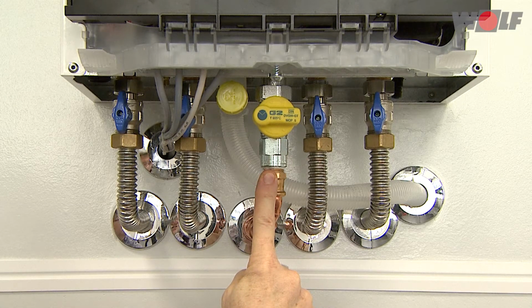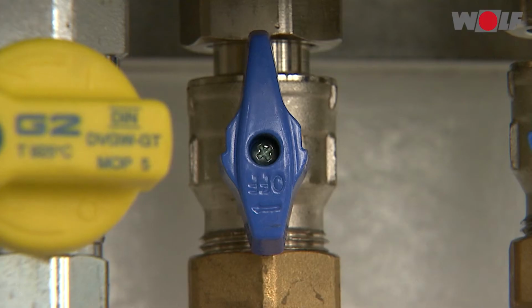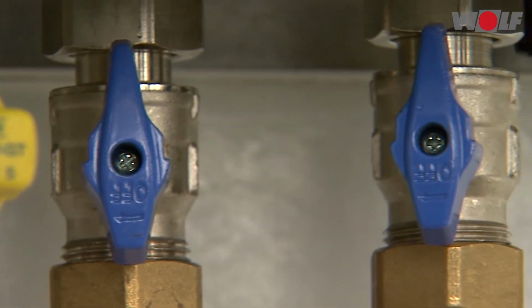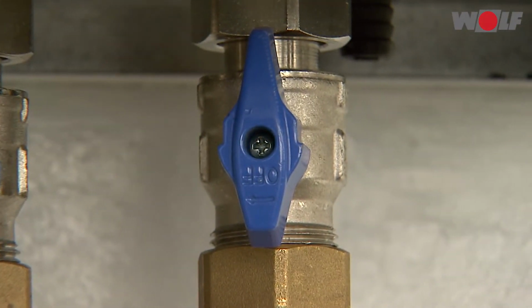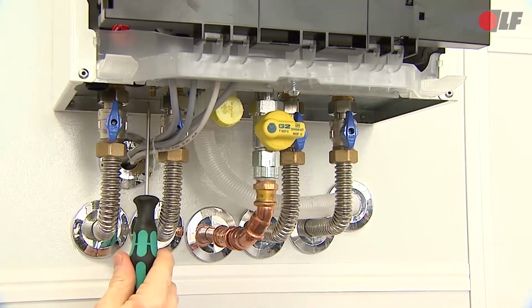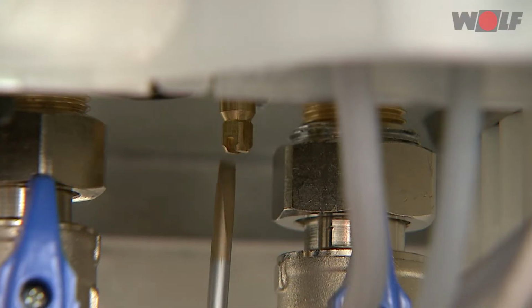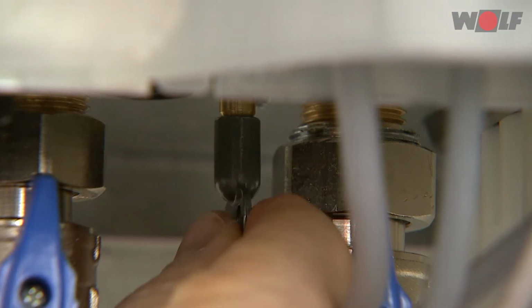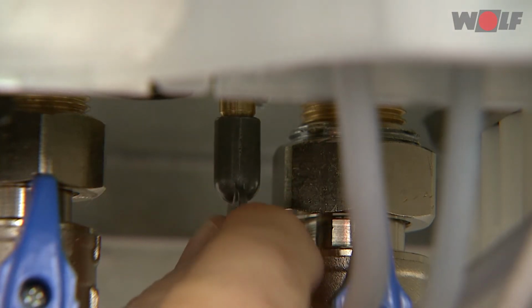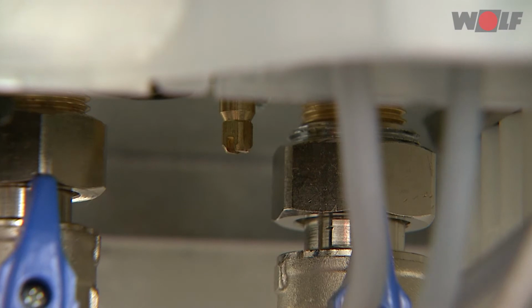Gas connection. Connect the gas supply line at the gas connection or the expansion joint using a 1/2-inch gas connection and an approved sealant. Ensure the supply line is stress-free. Filling the heating system via a filling facility. Open the fill valve on the filling facility. Fill the heating circuit via the domestic hot water circuit. Close the fill valve and test the entire appliance and the component unions for tightness.